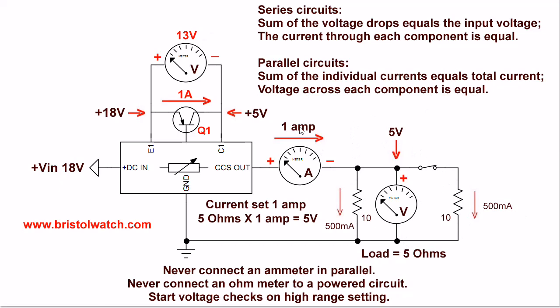As you are making these measurements let's note something. Never connect an ammeter in parallel. Do never, for instance, check a voltage in the amp setting. An amp meter has a real low resistance. You try checking a voltage, you just shorted out the circuit, maybe blew the fuse in your meter if you're lucky and didn't blow the meter.